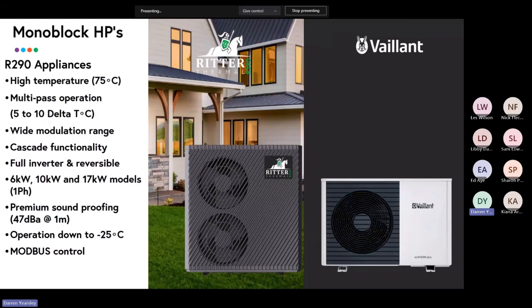So one of the other things with R290 appliances, they have a really, really wide operating range in terms of ambient air temperature. So they'll operate right down to -25. So the COP is terrible, but they'll still operate at -25. So the operating range is really good for these appliances. So they don't run out of legs once you go below 0 degrees. The performance curve is relatively flat.